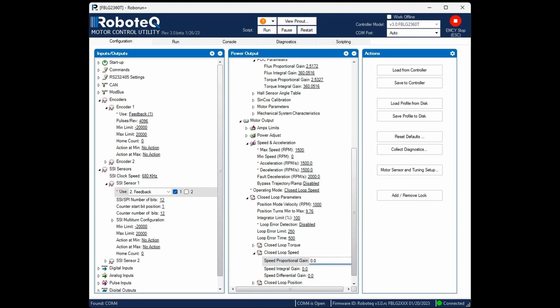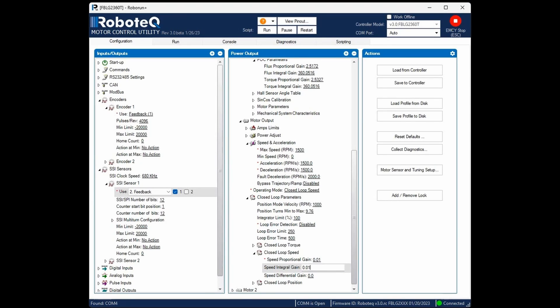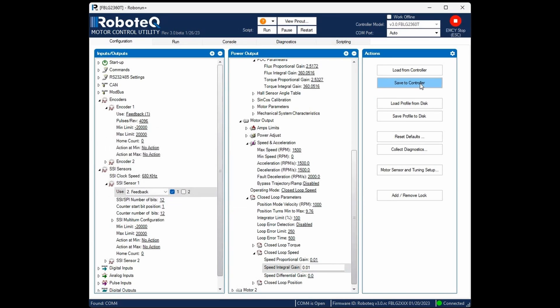In this video, we will set some preliminary PID gains to effectively enable the motor to reach its set point when operating without load. Begin by assigning a value of 0.01 to both the proportional and integral gains. This setting should provide an adequate response for most motor types.